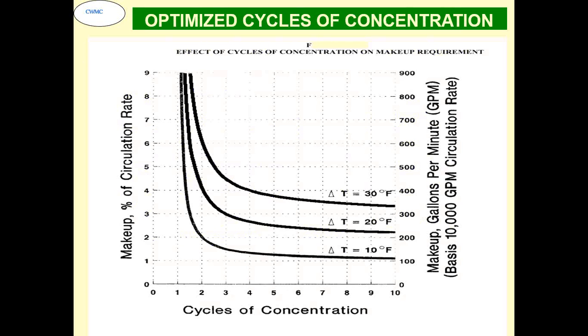See, we get the advantage if we are operating the cooling water systems at a higher cycles of concentration. But the practical thing that has been seen is, in most of the systems, an optimized COC of about 5 to 6 is there. Beyond that, normally there is not much advantage that we get, because in that case we have to use a very high quality of chemical, high dosages of chemicals, and then controls become difficult.